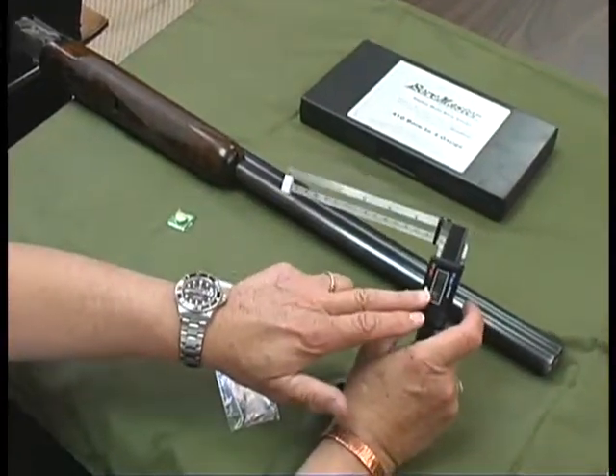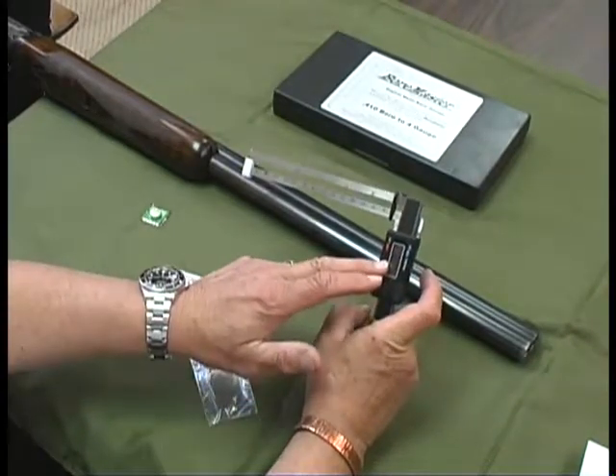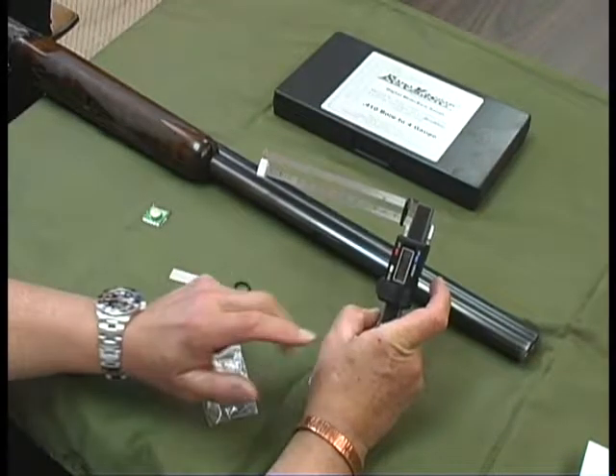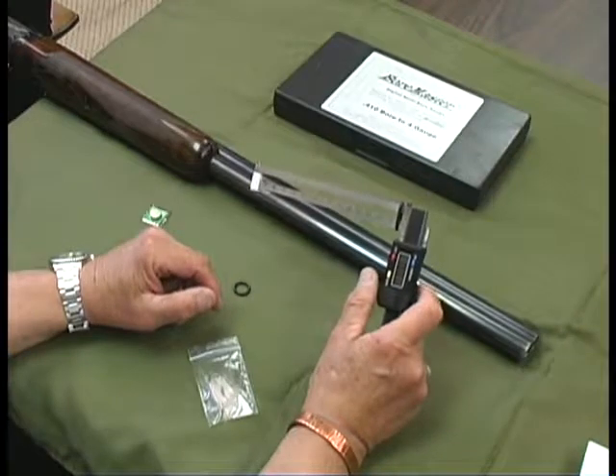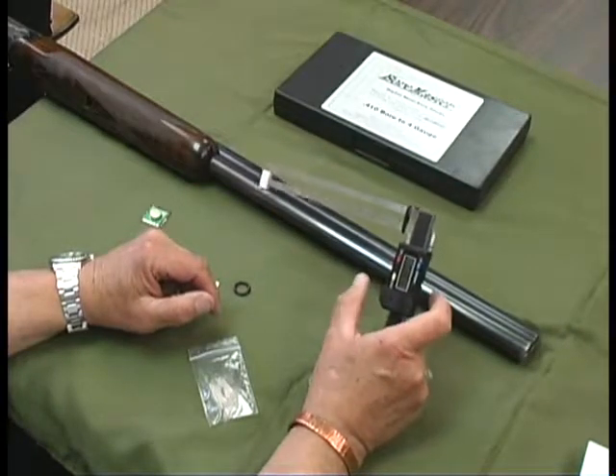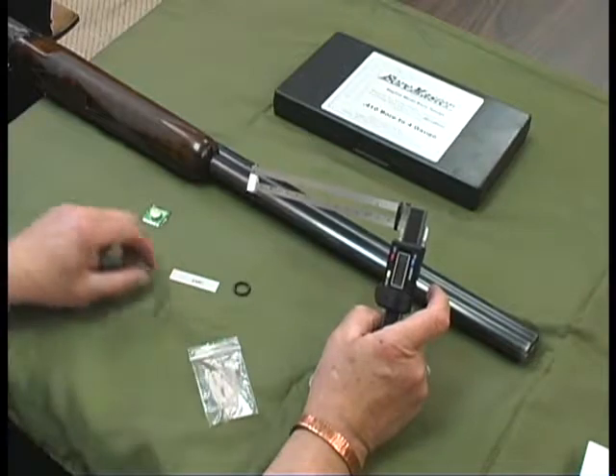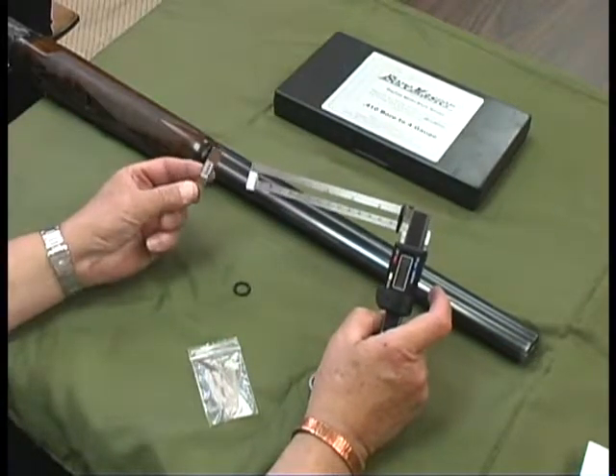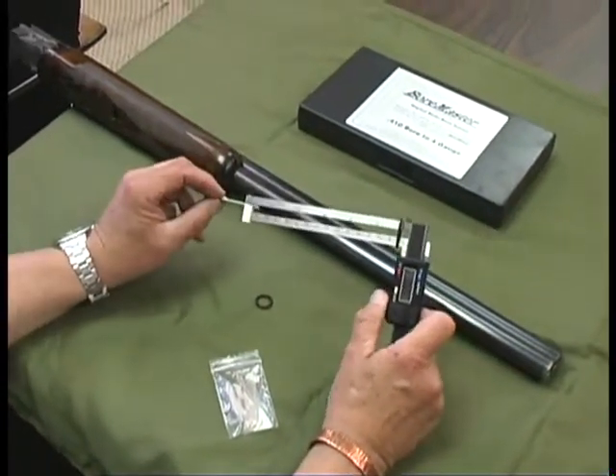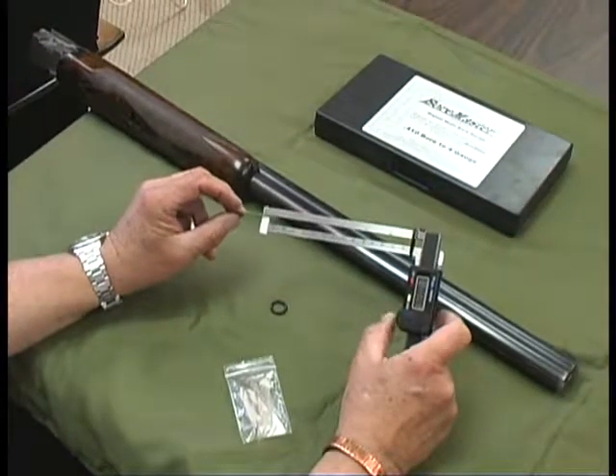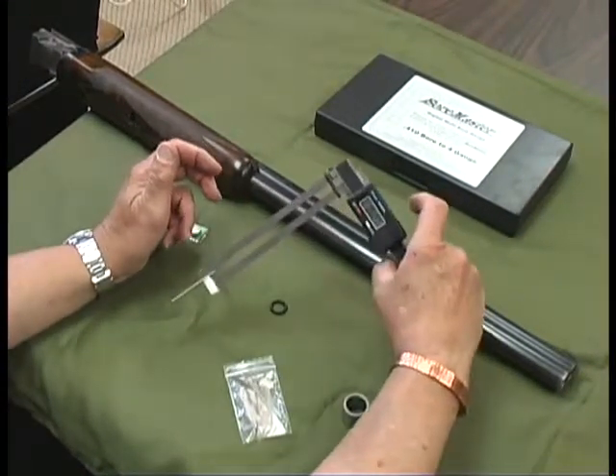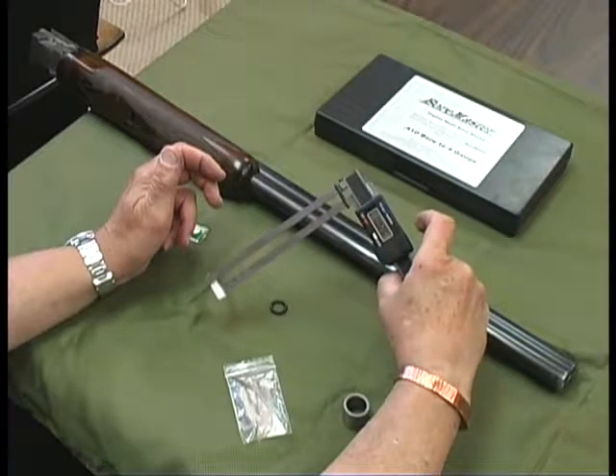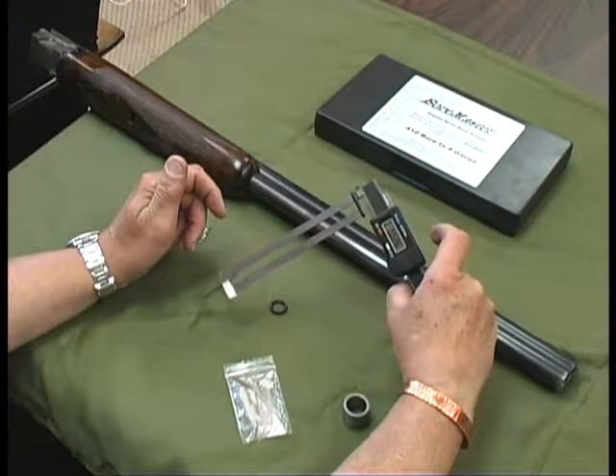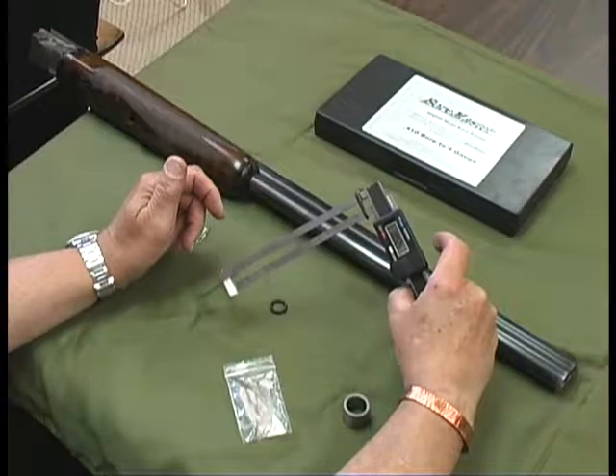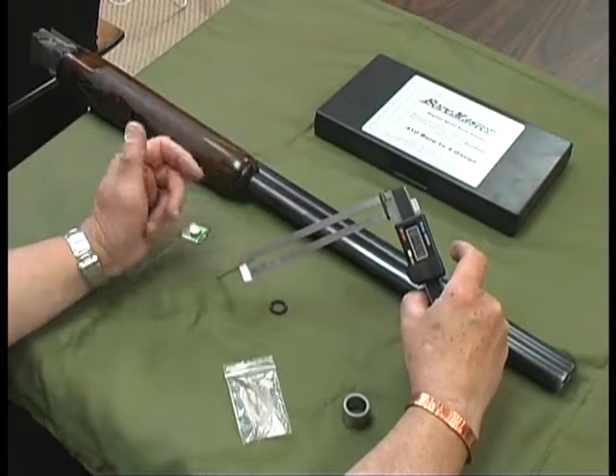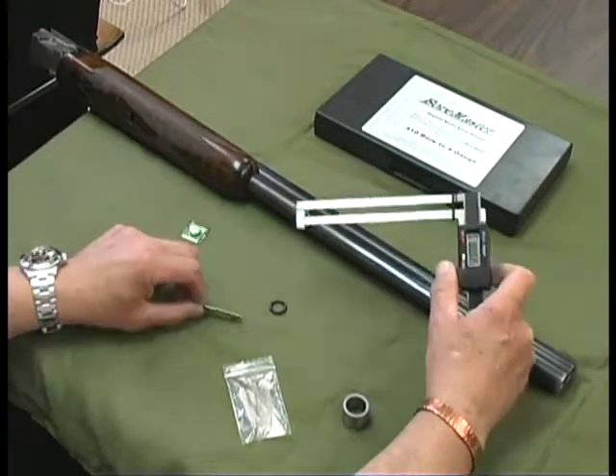The way we use this now is we zero, as we did before, but now this is a different zero point. Let it go back and forth and set it into the plastic piece. As you can see, it still reads 0. This is a 25 thousandths calibration strip, just in terms of proving that dimension. And here, as you could see, we're reading 26 thousandths, which is way close enough in terms of reading barrel wall thickness. So this is ready to read any barrel wall.